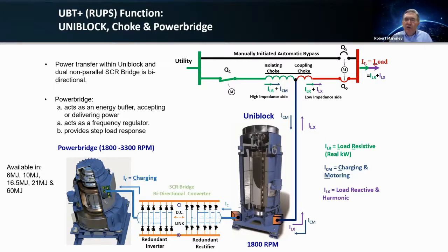You heard me talk about voltage regulation, harmonic mitigation, power factor correction of the UPS systems. But this is a parallel online architecture. So in the event of a frequency excursion, we're going to actually disconnect from the utility. We're going to go to the stored energy device, be it flywheel or batteries, and then we will correct back to the reference in the United States, 60 hertz frequency, and we can do that in anywhere from 1 to 5 hertz per second. That's an adjustable slew rate.